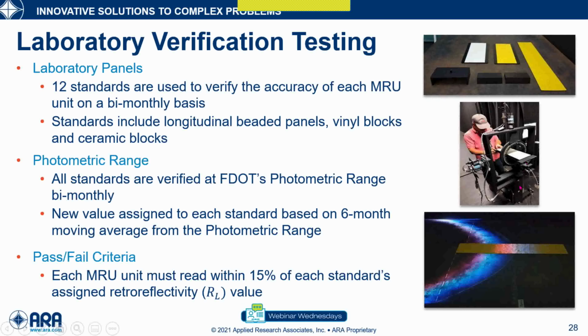So that panel goes back to the calibration bay where we check each unit. For instance, this panel has a known assigned value that was obtained from the photometric range. So the unit will measure it, and once a unit measures that known value, the criterion is that it should be within 15%. If it goes beyond that, it means that the unit has failed the laboratory verification. So what happens? I have to redo it, or we have to send the unit, meaning the MRU unit, to the manufacturer.